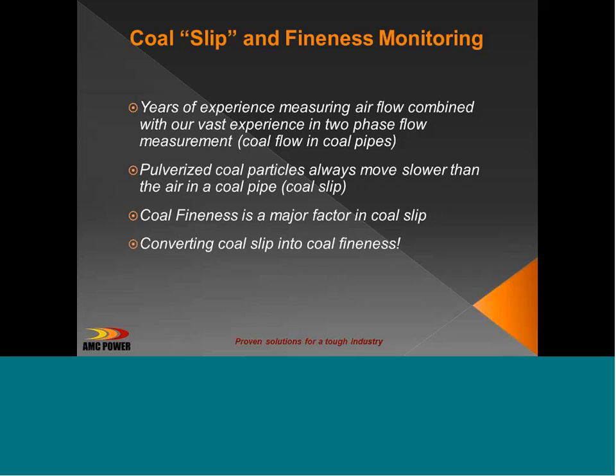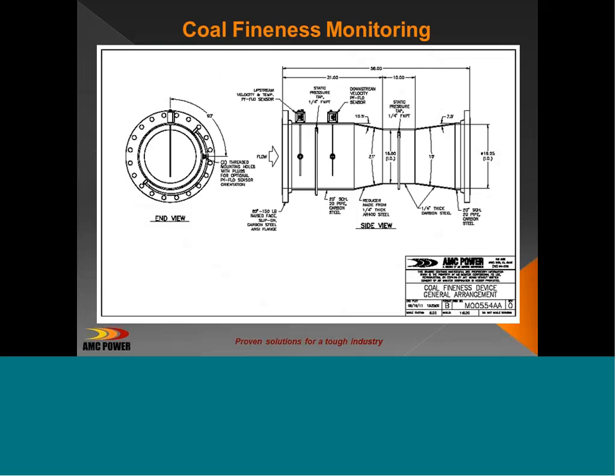So our challenge was to turn that slip, the speed difference between the fuel and the air, into a coal fineness measurement. This device is actually one that's being installed on a double-ended exhauster mill. Rather than in each of the individual pipes, this is in the main pipe coming off the pulverizer before it riffles to multiple pipes. In this section of duct is the venturi. It's a very slight beta angle venturi, and it's an AR material so that we're not going to have a lot of wear. We're measuring the velocity of the air, and this was pre-calibrated in a wind tunnel so that we know exactly what the velocity of air is associated with the DP through this venturi.